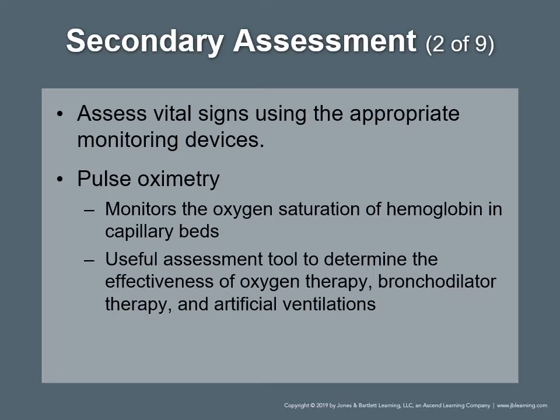Now, a regular pulse oximeter does not differentiate between those gases. You have to have other oximeters or other probes to check other gases, but it will give you false high or low readings based on the saturation concentration of whatever is hanging onto that hemoglobin.